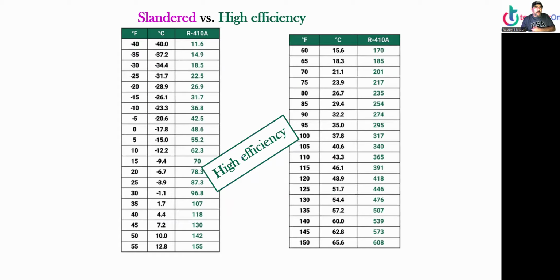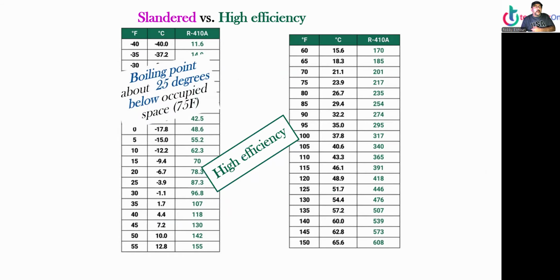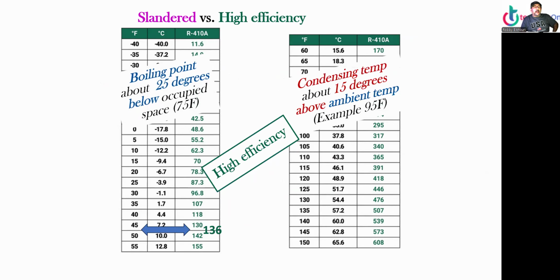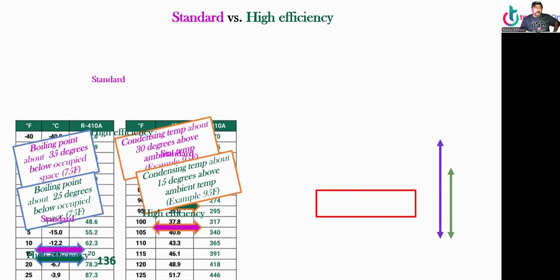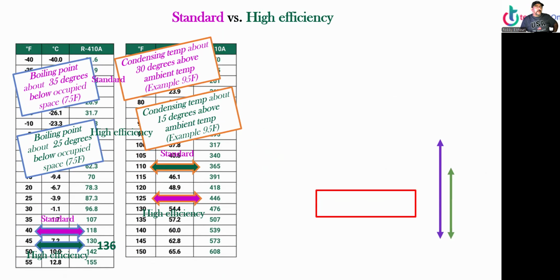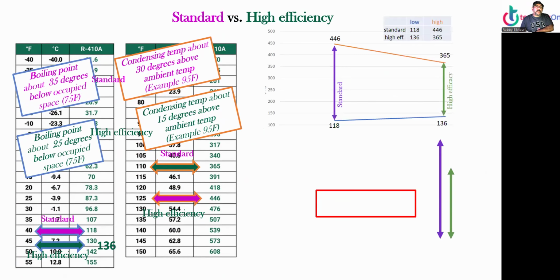446. Now, high efficiency, we raise the boiling point. It's about 25 degrees. Boiling point now is at 50 degrees, at 45 degrees, 136 pressure. And then your discharge temperature is less now. Discharge pressure is less. It is at 365 because high efficiency runs with low pressure higher, high pressure lower, lesser compression ratio. So that's comparing standard and high efficiency. There's a compression ratio. There we go.